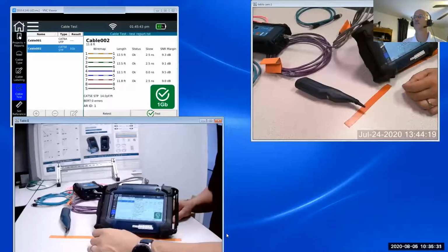As you can see here, we have a passing 1 gig cable. I can see the length of the entire cable as well as the length of each pair, and that there is a shield. I can see acceptable signal to noise ratio, acceptable delay skew, and an acceptable BERT test with 0 errors. This is a 1 gig cable, and I can feel confident in it.